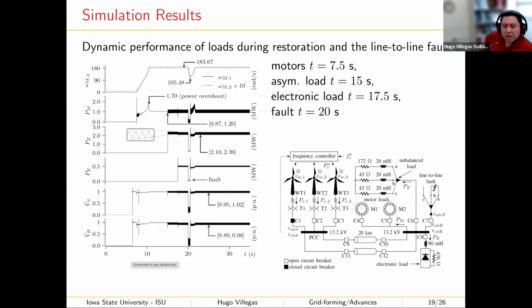And I have to confess that at the beginning, when I was taking this project, I failed. I failed several times. Actually, I was testing, for example, some prototypes of grid forming controllers, and I was testing only one turbine. Then I was doing the restoration, everything with one turbine, and it worked fine. And then I added a second turbine, and then it failed. And especially it failed when I was starting up motors.